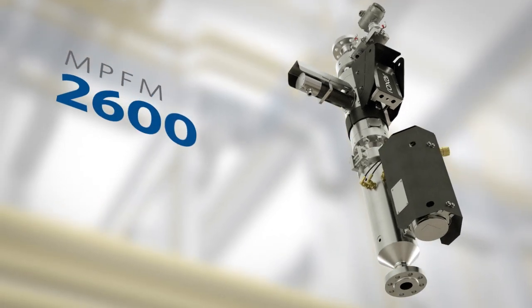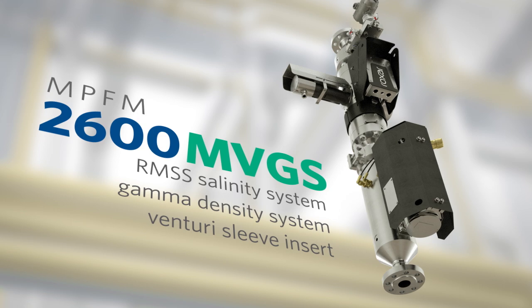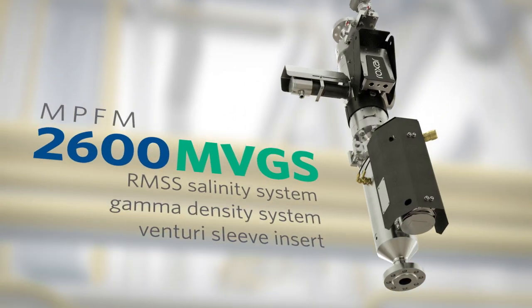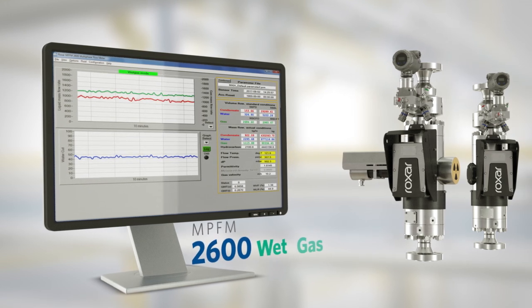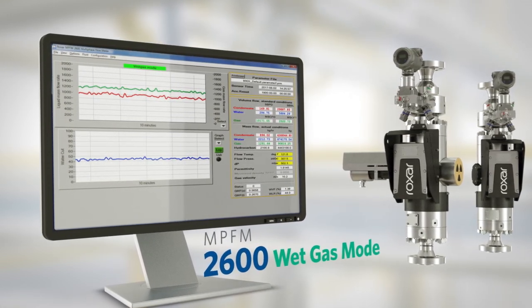The MPFM 2600 MVGS adds the RMSS salinity system, intended for wells with expected changes in produced water salinity. It provides direct water conductivity measurements to eliminate the need for sampling. And the wet gas mode extends the measurement range of up to 100% gas volume fraction.